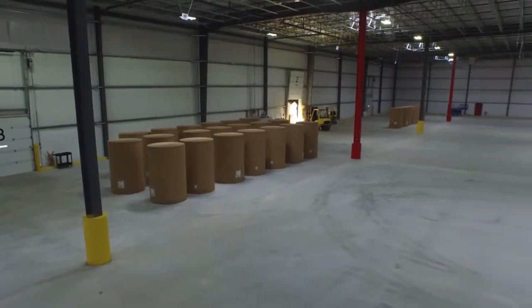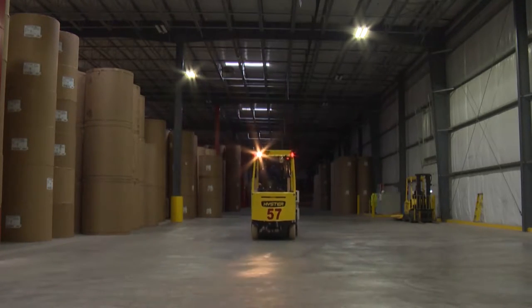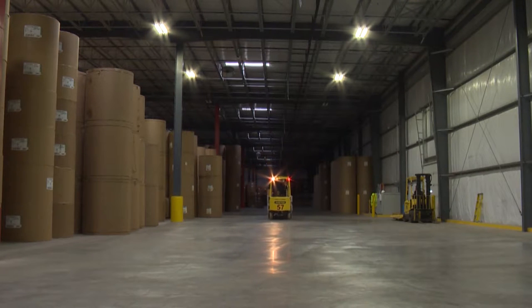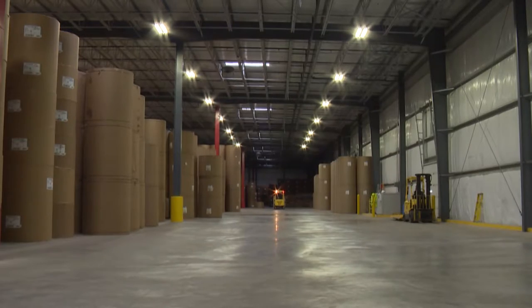The second item we did was look at the lighting system. We put in 32 skylights, two foot by ten foot — a special skylight that accelerates and broadens the light coming through. Those 32 skylights throw enough light in during the day, and we coupled that with a light-harvesting and motion-sensing module on the side of the LED fixture. It's programmed to turn a light on if someone gets close enough through motion sensing, but if there's enough light coming into the building, that light will never go on.